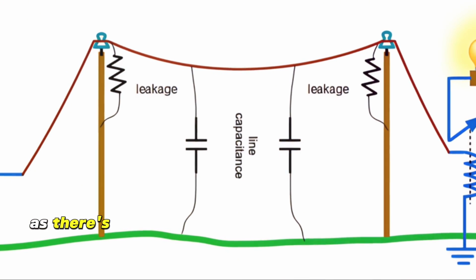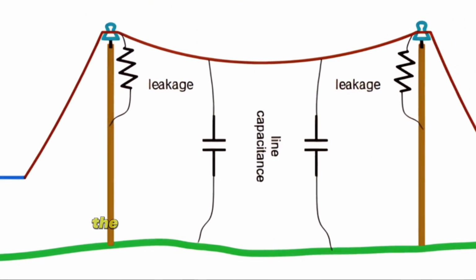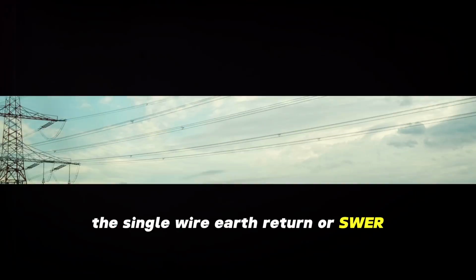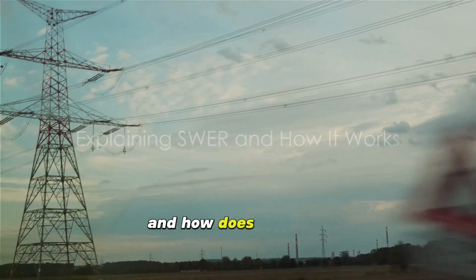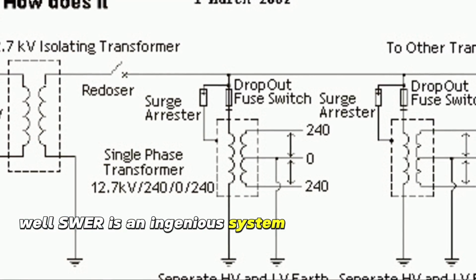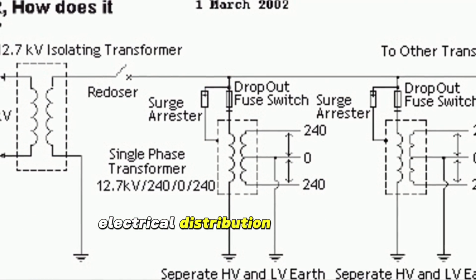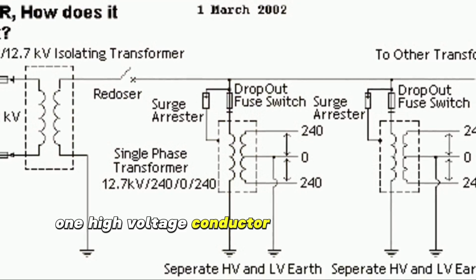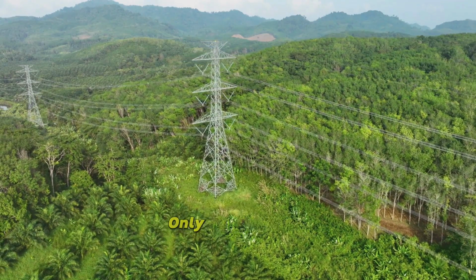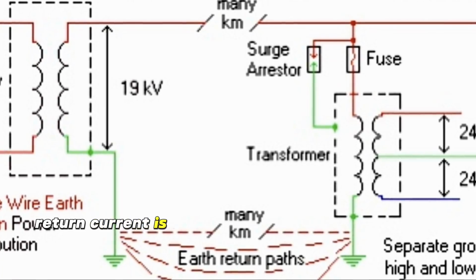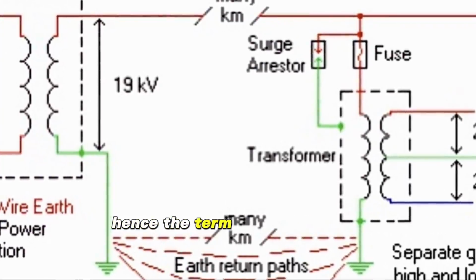But fret not, as there's a system that addresses these limitations: the single wire earth return, or SWER. So what exactly is SWER and how does it work? Well, SWER is an ingenious system that saves costs in AC electrical distribution by using just one high voltage conductor for the power grid. Yes, only one. The AC return current is cleverly routed through the earth, hence the term earth return.